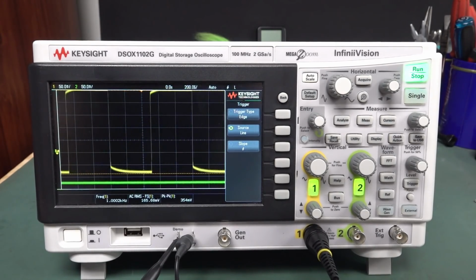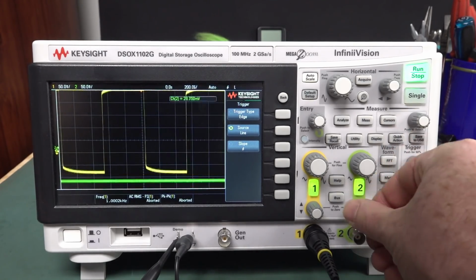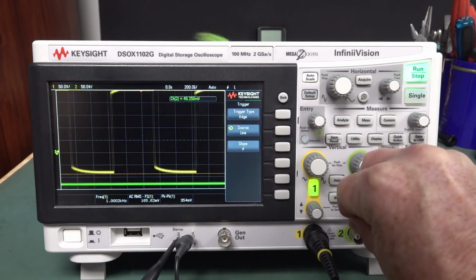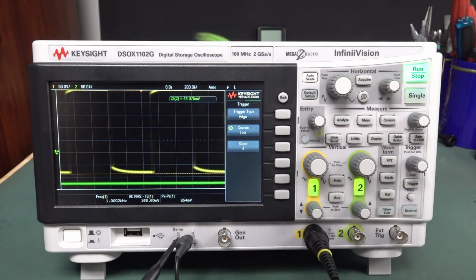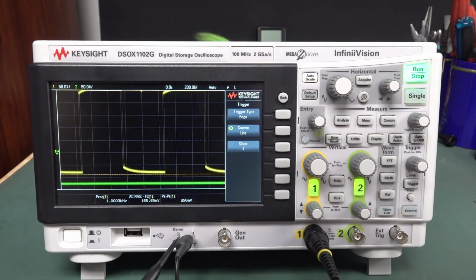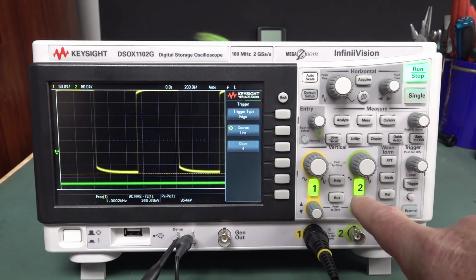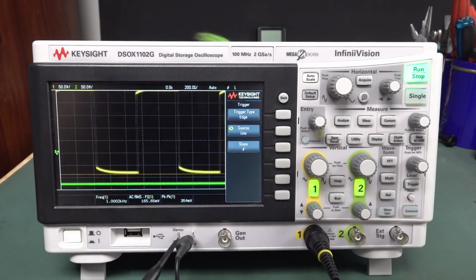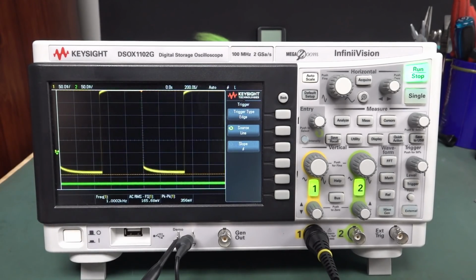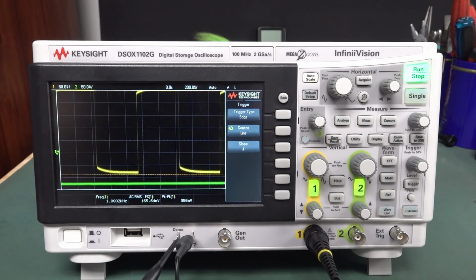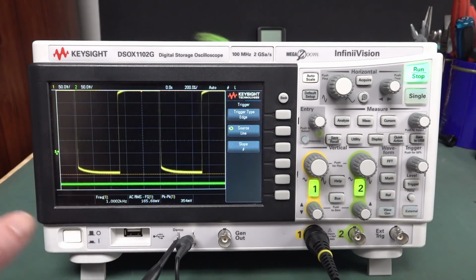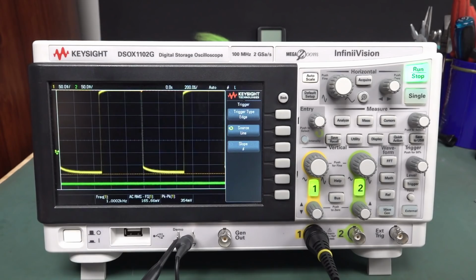That's weird, because I would have expected the DC offset to be generated when you turn your vertical position control here. It adds a DC offset value to the signal being measured, and I thought that would have been generated within the channel itself. So, we just saw a reversal of direction there. So slight drift between the 50 hertz mains and the 1 kilohertz internal. It's going to drift back. Oh, lovely. Anyway, that's fascinating.